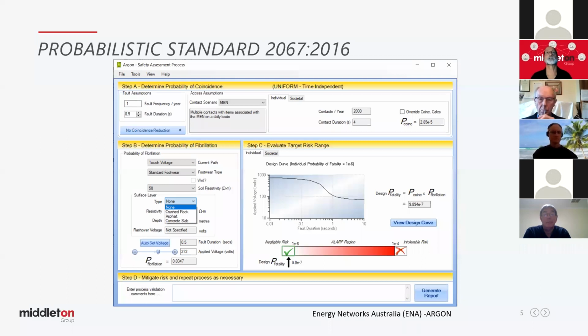So that sort of outlines determining the probability of coincidence and the probability of fibrillation. And on the right-hand side there, you can see a curve and that formula: the probability of fatality is equal to the probability of coincidence times the probability of fibrillation. And it's interesting to have a look at that curve there. The steepest part is in between half a second and a second. If we look at our heartbeats once a second, the longer the fault duration is while you're contacting a surface with that touch voltage on it, the more likely that voltage and that current through your heart is going to be at not a nice time for your heart. And it'll coincide with the part in the heartbeat that causes ventricular fibrillation if your heart's constricted by current flowing through it at the time.